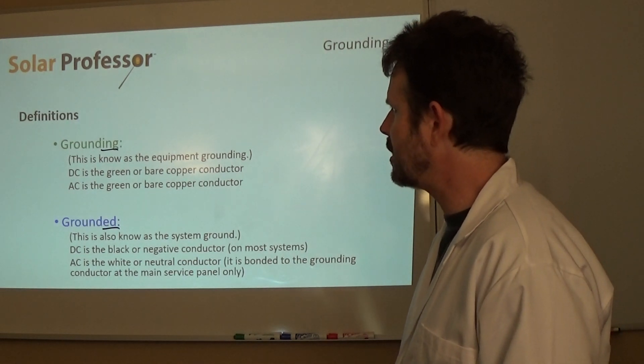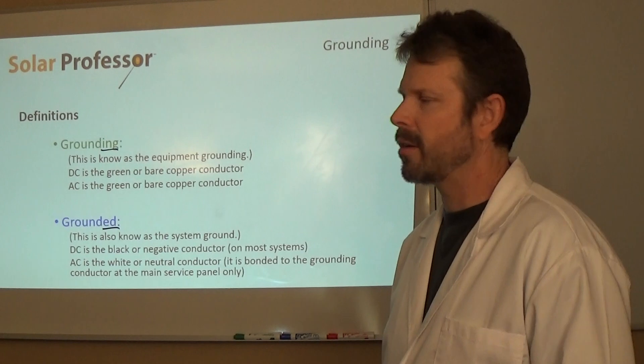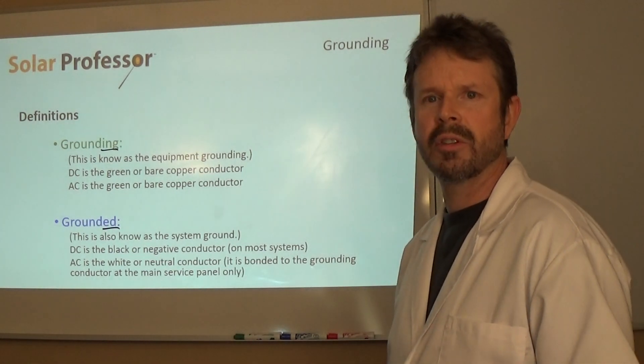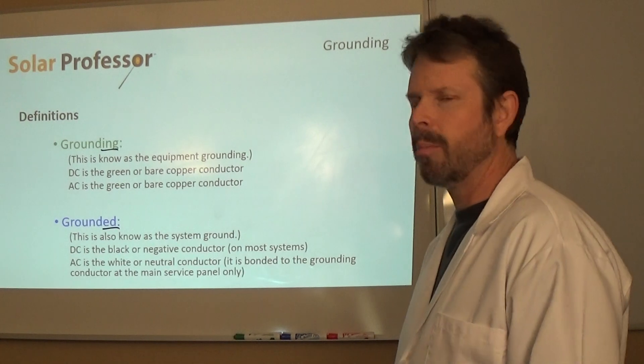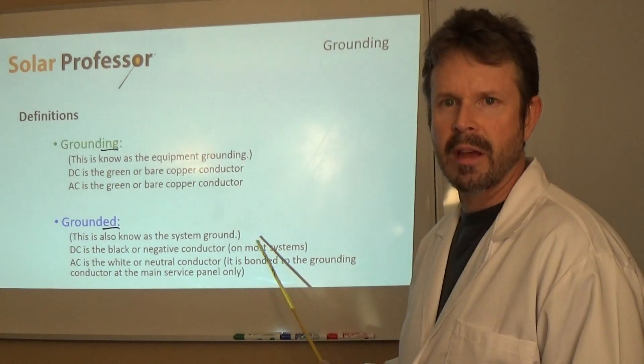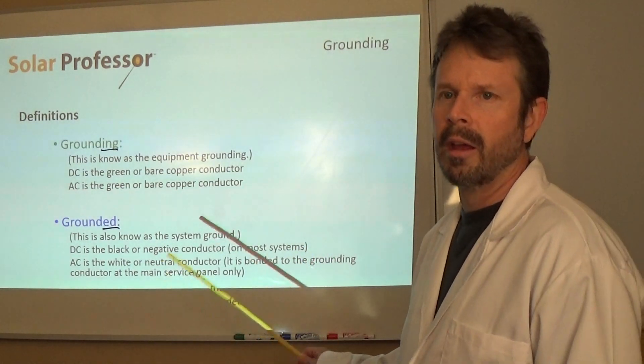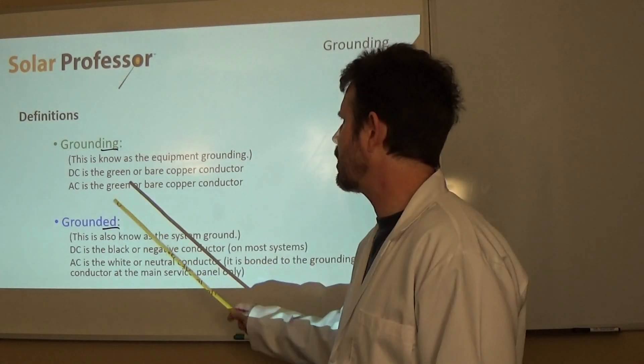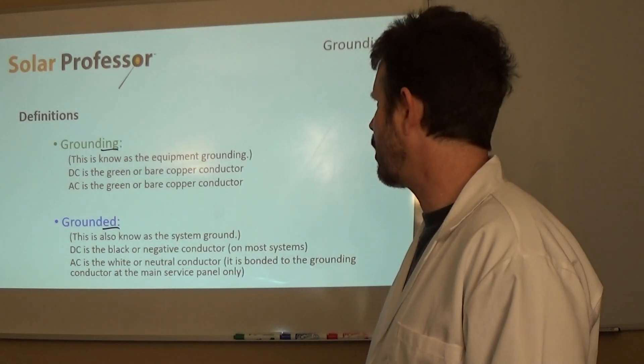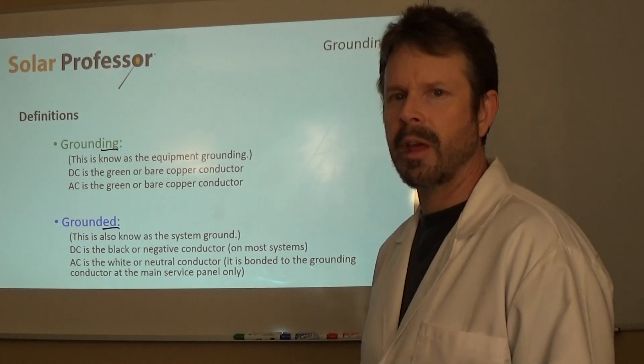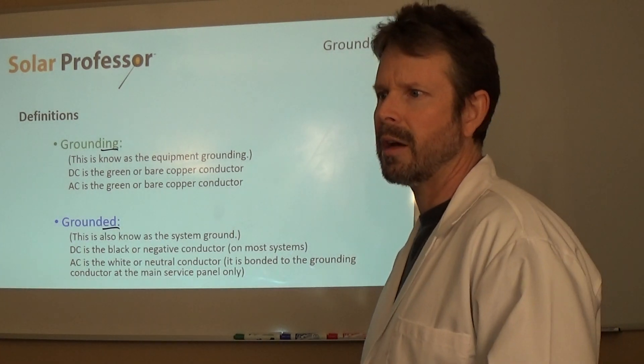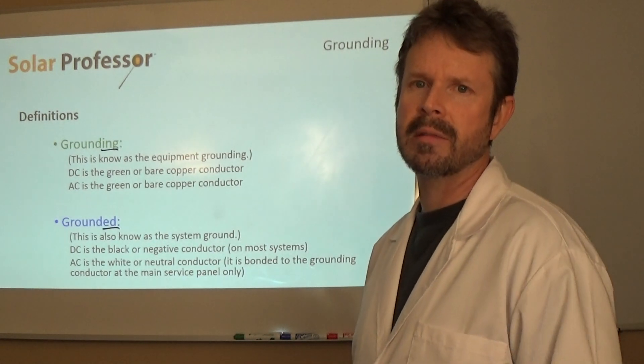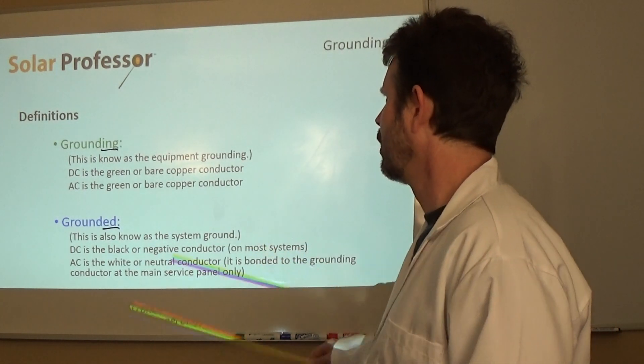On the DC side, the grounding conductor is the green or bare copper conductor. You've seen that in systems and wiring diagrams. On the AC side, it's the same thing — green or bare copper. Sometimes in older or newer equipment you'll see it green with a yellow stripe, which is also acceptable. All of that is the equipment grounding conductor.